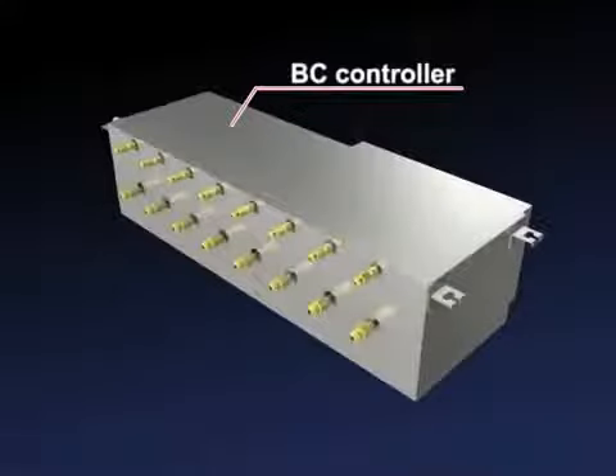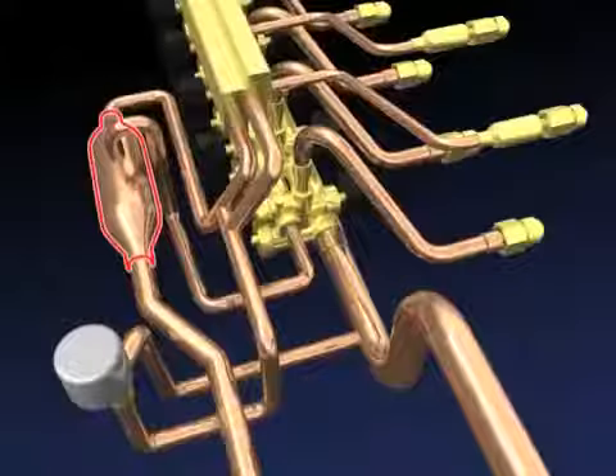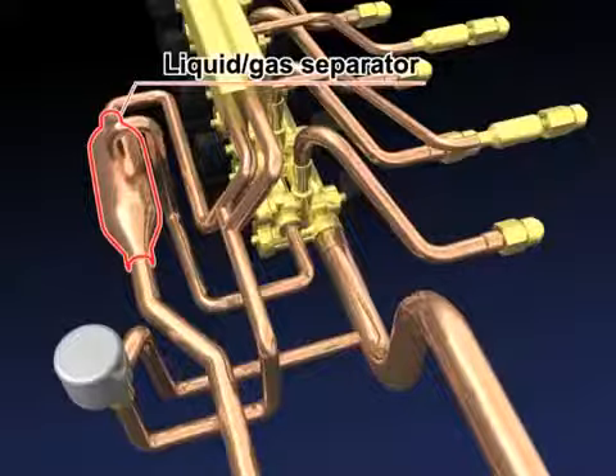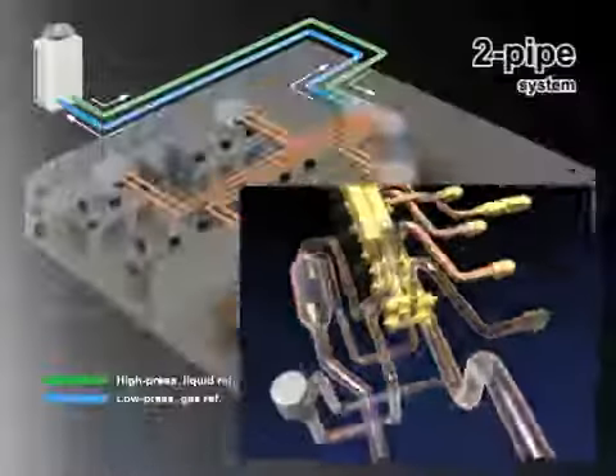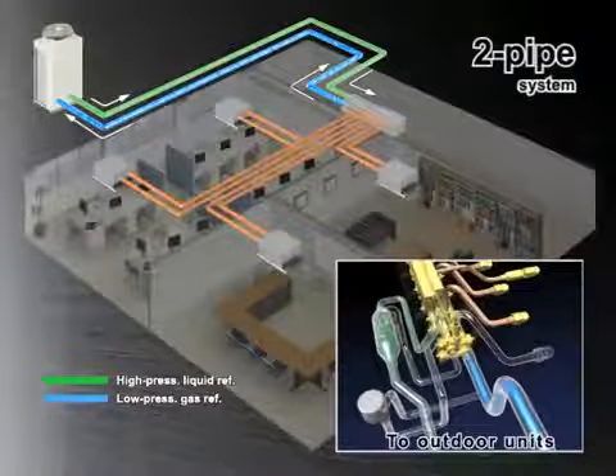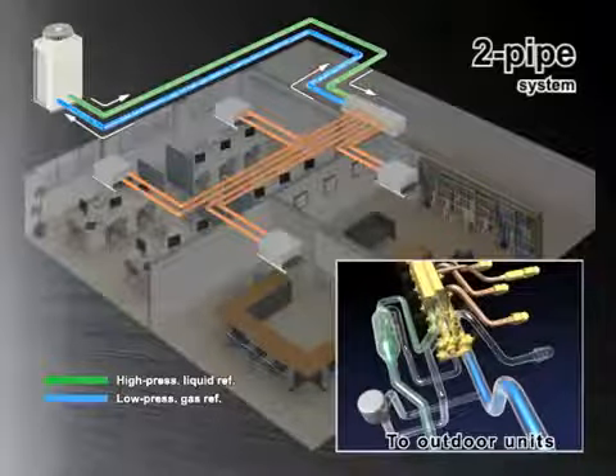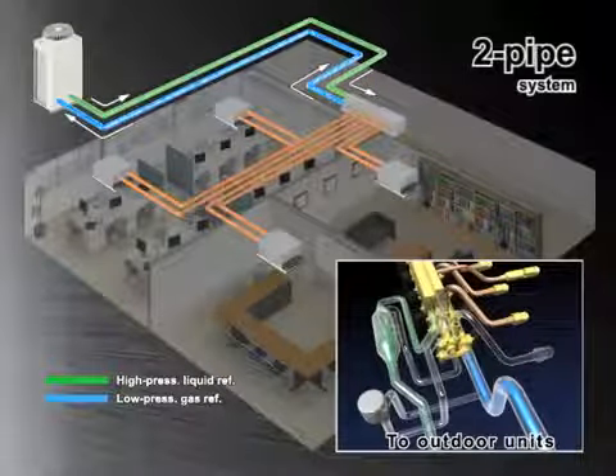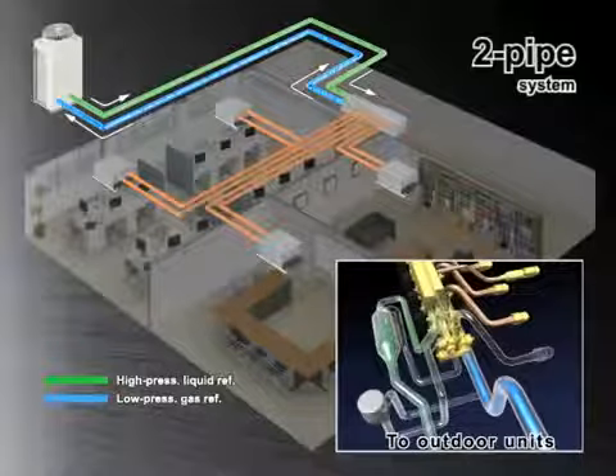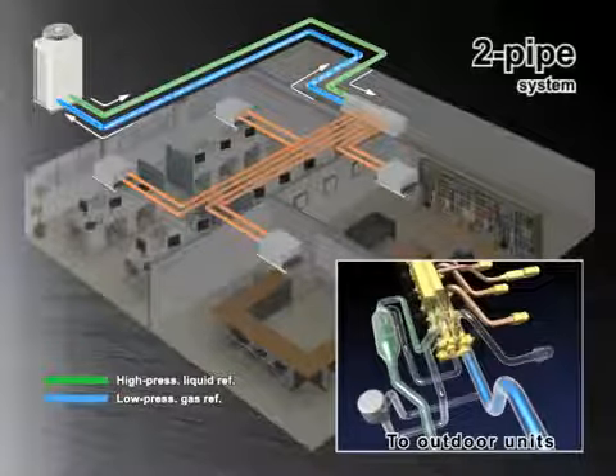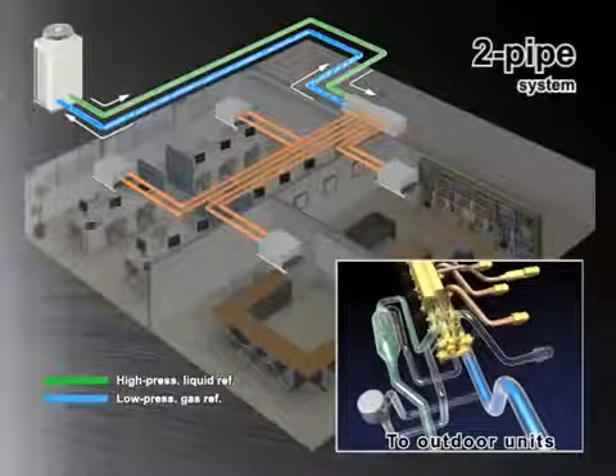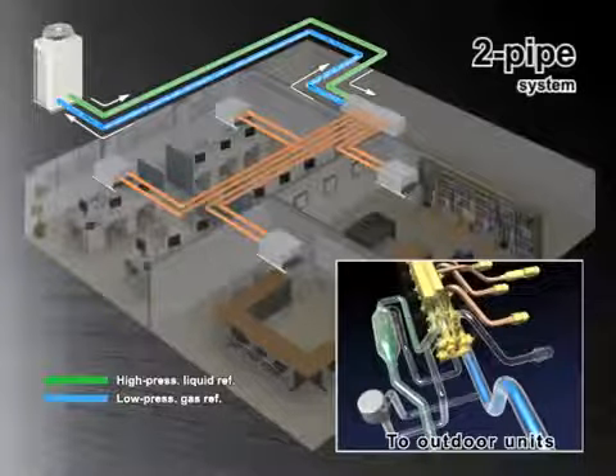With the 2-pipe system, the BC controller houses a liquid and a gas separator, allowing the outdoor unit to deliver a mixture of hot gas for heating and a liquid for cooling, both through the same pipe. The right amount of phases are delivered to each indoor unit with a LEV, short for linear expansion valve, depending on the individual requirement of either heating or cooling.